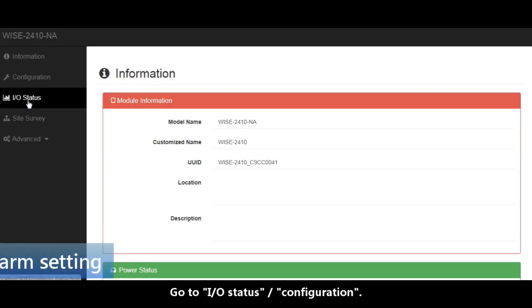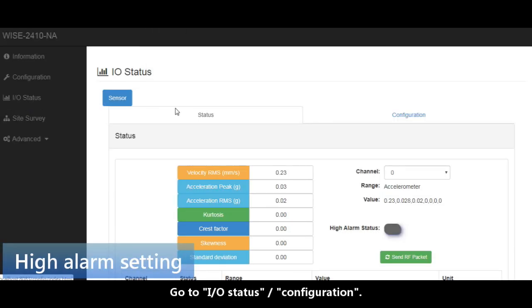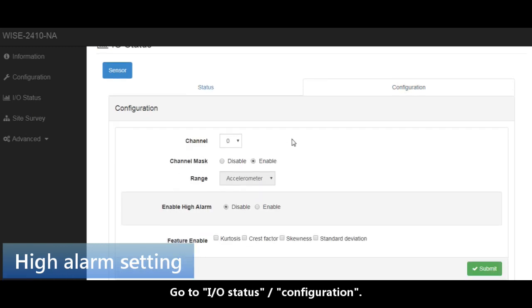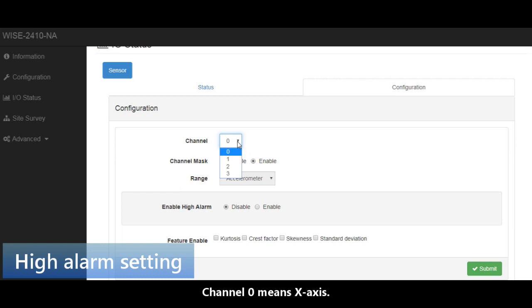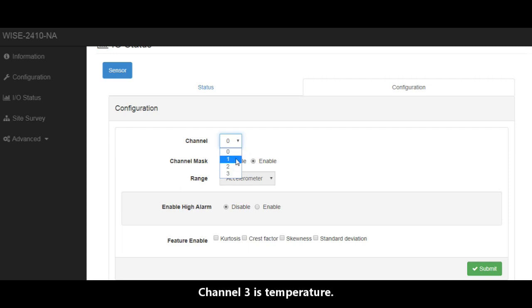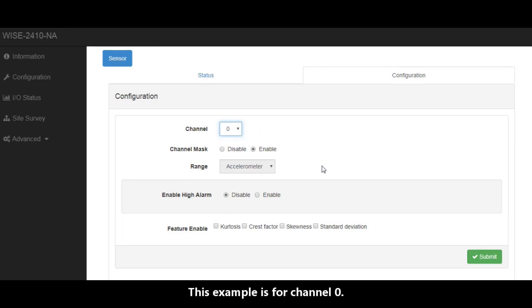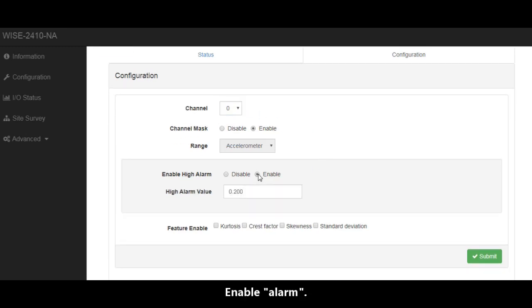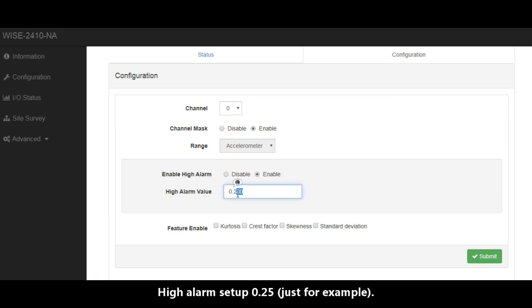Go to IO status configuration. Channel 0 means X axis. Channel 1 is Y axis. Channel 2 is Z axis. Channel 3 is temperature. This example is for channel 0. Enable alarm. High alarm value setup 0.25. Click on submit.